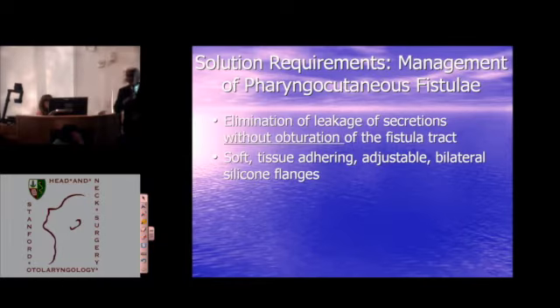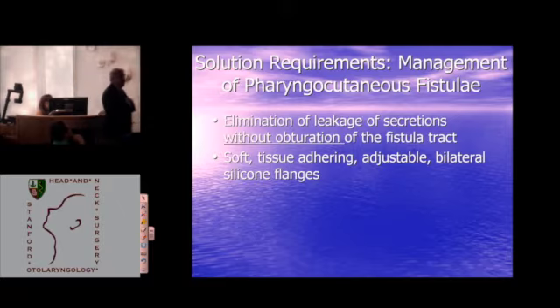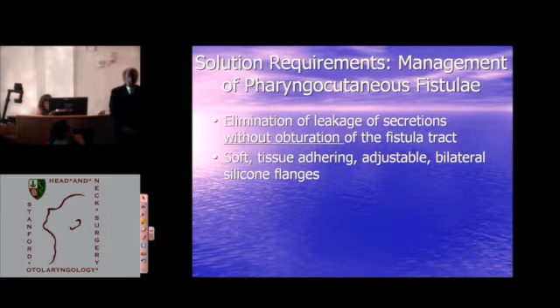And fortunately, I kept all of that data on all of the surgeons around the country that I made fistula devices for, because once we got to the FDA, thinking that we'd get through on a similarity to other devices like a salivary bypass tube for fistula control or flanges on a voice prosthesis, the committee said, well, I think we'd like to have some specific clinical data. I said, I just happened to have some of that.